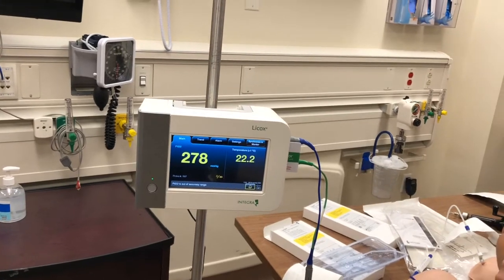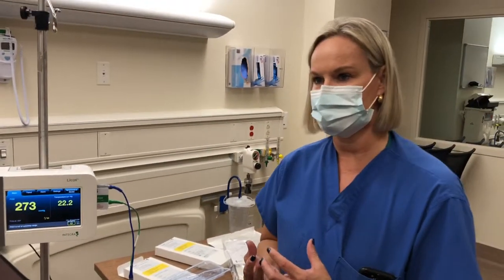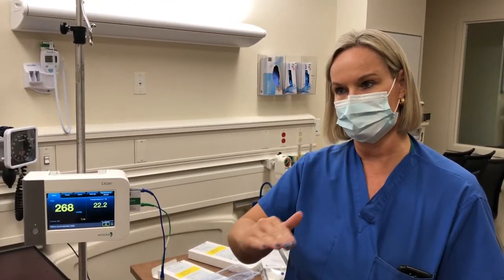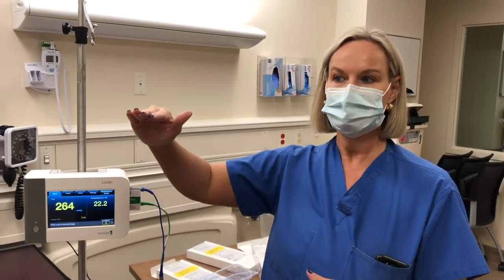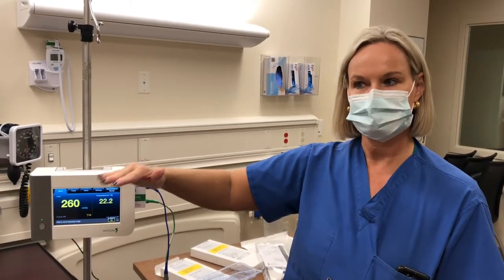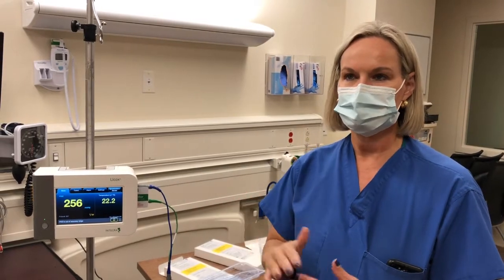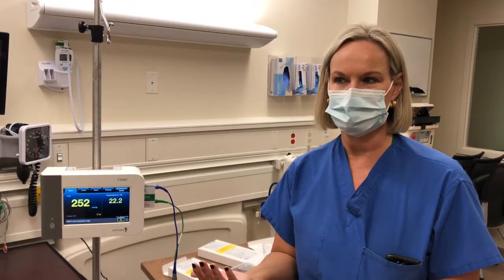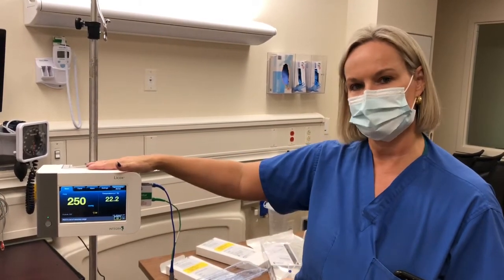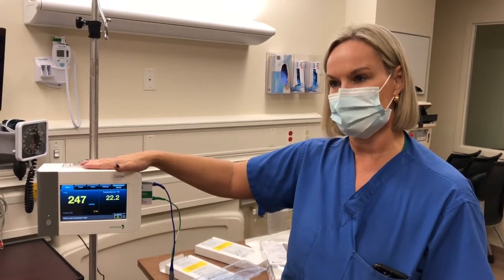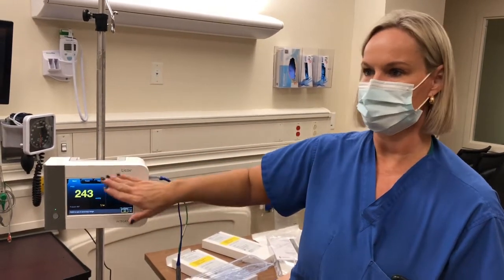I do want to let you know that in about 25% of the cases you will sometimes see it start at a very low number, and then it will drift up. Again, you're waiting for it to plateau. And in the meantime, 20 minutes to 2 hours really goes by pretty quickly because you've turned this on. Remember I told you in the last video that this is warming up for about 3 hours because it's calibrating temperature.